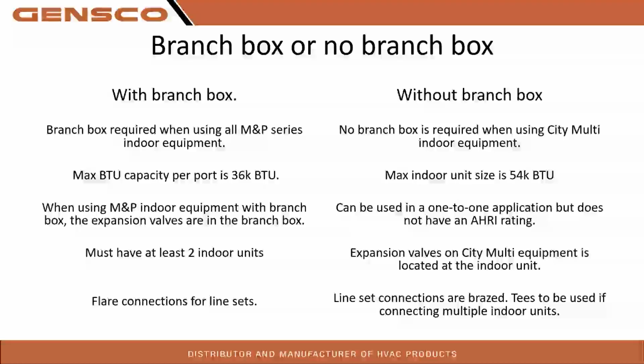Without a branch box, we can use City Multi indoor equipment on a Smart Multi heat pump. Again, that comes back to your expansion valve positions. City Multi would be like your PVFY air handlers. Pretty much anytime you want to go over that 36,000 BTU for a single indoor unit, City Multi without a branch box is the way you're going to want to go. With City Multi, the max indoor unit size is 54,000 BTU, which is our PVFY 54. So if you're looking for something a little bit bigger, that is an option there.